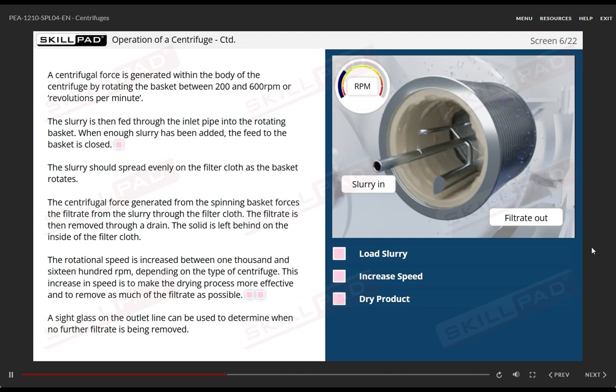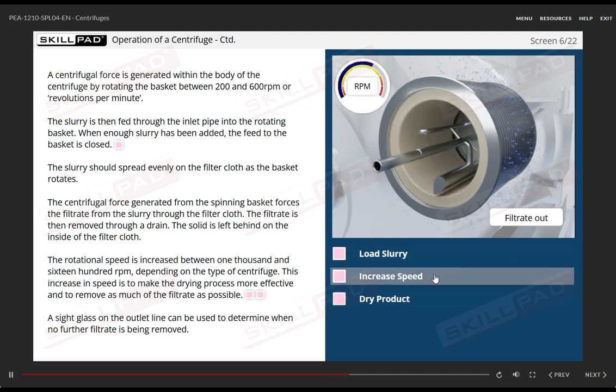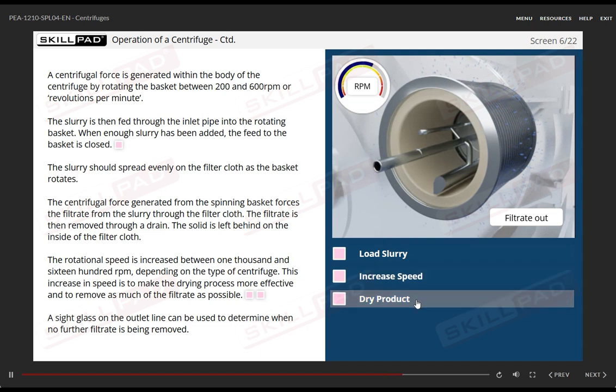The centrifugal force generated from the spinning basket forces the filtrate from the slurry through the filter cloth. The filtrate is then removed through a drain. The solid is left behind on the inside of the filter cloth. The rotational speed is increased between 1,000 and 1,600 RPM, depending on the type of centrifuge. This increase in speed is to make the drying process more effective and to remove as much of the filtrate as possible. A sight glass on the outlet line can be used to determine when no further filtrate is being removed.